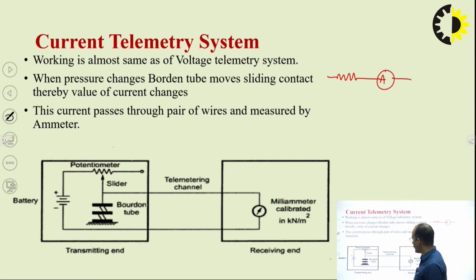Here again it's the same Bourdon tube: pressure applied on it is converted into displacement, and that displacement changes the slider position. This changes the overall current flowing in the circuit, and you can see the ammeter or current metering part is connected with the transmitter through the wired channel in series.